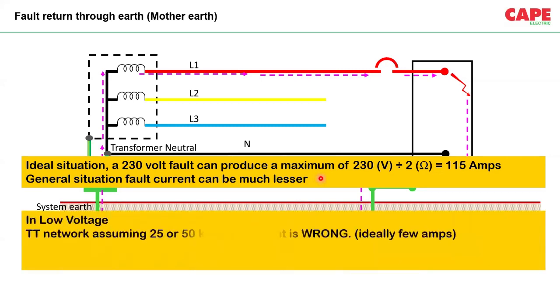Number two, in low voltage, in a lot of places, as I said, metro railways, most of the metro railways across India, for signaling application for a UPS neutral or UPS body or some of the S&T equipment, they make a large grid, assuming that 50 kiloampere fault current goes to earth. I really don't know who gave this idea to them. But as a result, the whole safety is violated in that particular case.